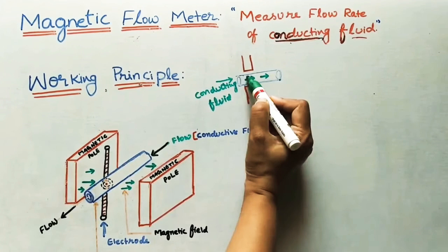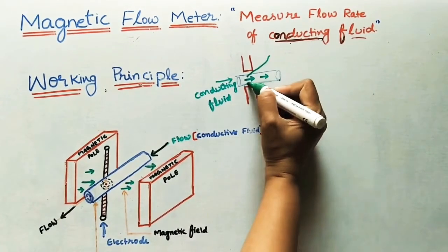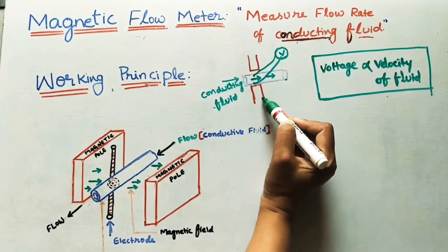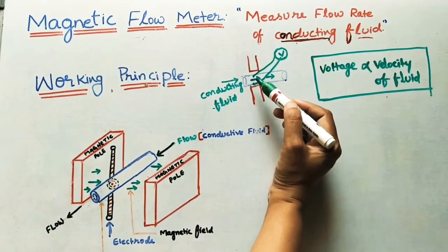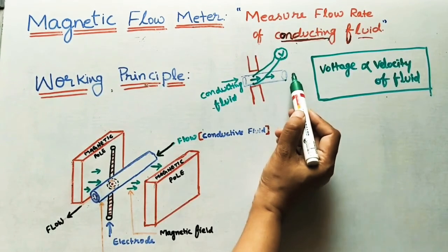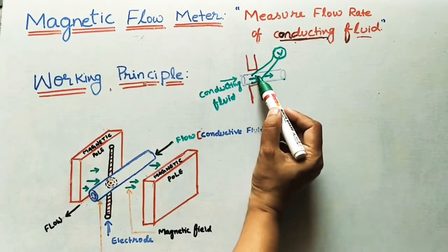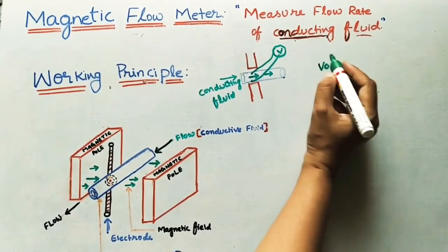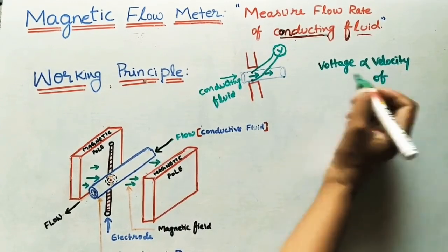Whenever this conducting fluid cuts the magnetic field, voltage will generate. To find this voltage, we connect two wires or terminals to the non-conducting pipe and connect a voltmeter. The flow is perpendicular — transverse — to the magnetic field. This is important: the flow is perpendicular to the magnetic field. Whenever this conducting fluid cuts the magnetic field, it induces a voltage that is proportional to the velocity of the flowing conducting fluid.